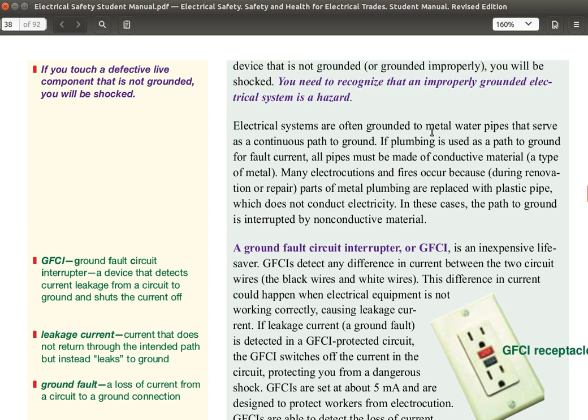Electrical systems are often grounded to metal water pipes that serve as a continuous path to ground. If plumbing is used as a path to ground for fault current, all pipes must be made of conductive material, a type of metal. Many electrocutions and fires occur because during renovation or repair, parts of metal plumbing are replaced with plastic pipe, which does not conduct electricity. In these cases, the path to ground is interrupted by a non-conductive material.